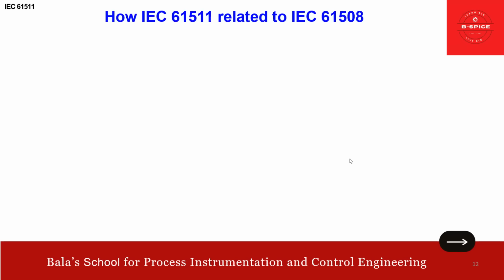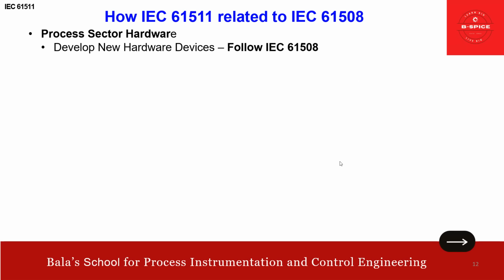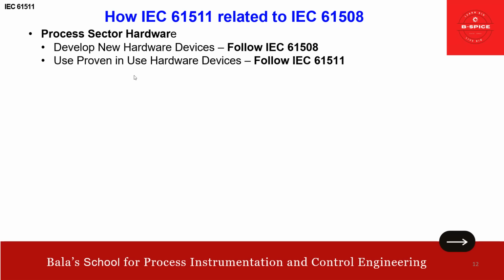Now, how is IEC 61511 related to IEC 61508? You see, friends, there is some correlation actually. In the process sector, to develop new hardware, we follow IEC 61508. To use proven-in-use hardware devices, follow IEC 61511. You are getting it, right? When you develop a new hardware device, you have to follow 61508.